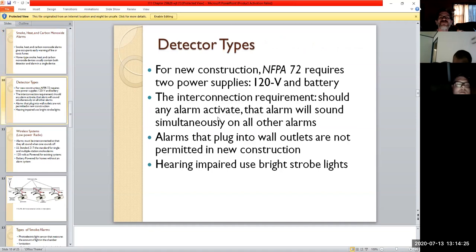So what are some of our rules? Referring back to NFPA 72 here, if you install in a brand new construction, every single detector has to have two power supplies, essentially. The home system, which is your 120 volts. So now you're going to run a separate branch circuit for your alarm system, for its own overcurrent protection and everything else. And these will actually have outlet boxes installed for them.